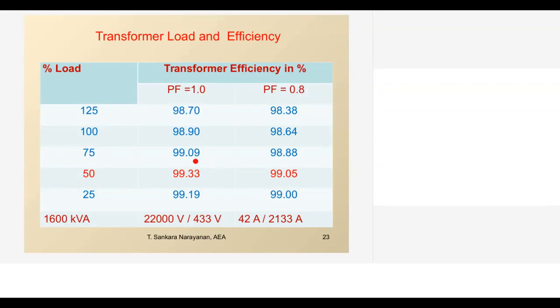That is why most utility companies have a thumb rule. For distribution transformers, the loading will be 50 to 60%. For power transformers, loading can be more than 75 to 85%. Once the transformer has internal characteristics like that, I may not have the opportunity to always replace a transformer, but I can account for all the transformer losses.